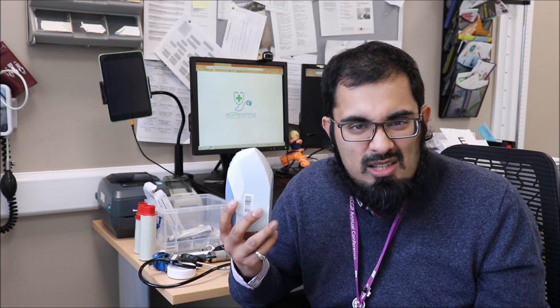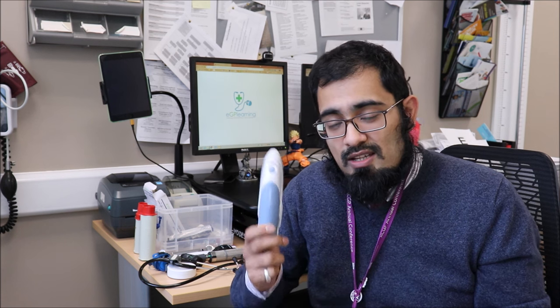Similarly, if patients are wrapped up warm and have been sitting in the waiting room, their surface temperature may read higher than expected — that's more noticeable with surface thermometers than in-ear ones. In terms of method, the majority of people tend to prefer in-ear thermometers for ease of use, though axilla can be more effective and more accurate, particularly for younger children.